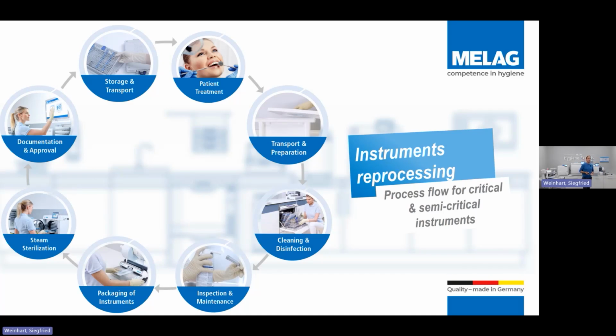We then have inspection and maintenance, looking at our dental handpieces. At what point do we inspect and lubricate our dental handpieces? Well, it is always before the sterilisation point. We are cleaning them, usually with alcohol-free wipes or through an automated process. We are then oiling them internally and cleaning them internally. We are then processing them through the sterilisation process. We then package our instruments. Now, the guidance changed many years ago: it doesn't matter whether you pouch pre-autoclave or post-autoclave, you're still getting a year's storage. So in retrospect, it doesn't matter.